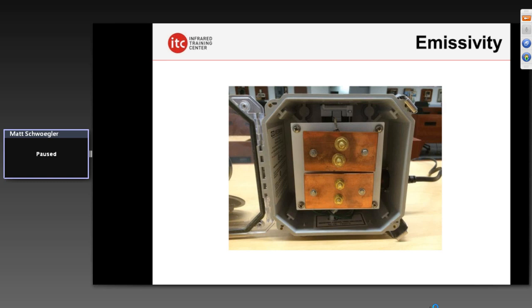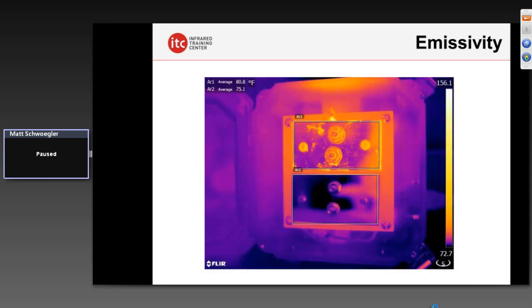Going back to our bus bar lab — I took two area boxes showing you the apparent temperature difference between the top phase and the bottom phase. It appears to be about a 5-degree temperature difference — 80 on the top phase and 75 on the bottom. But the important thing to focus on is the pattern: there's a very subtle difference between the two, and this is a low-emissivity surface. It's not emitting its energy very efficiently at all — it's a very poor emitter and a very good thermal reflector. So most of what you're seeing really has nothing to do with the actual temperature of these two surfaces.